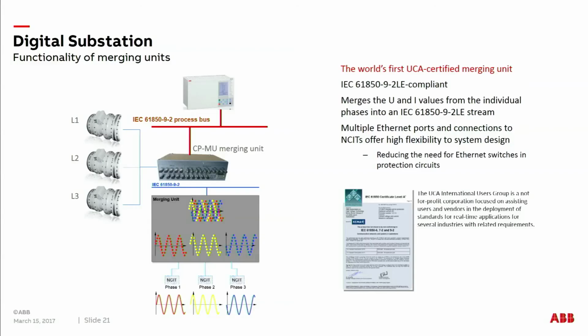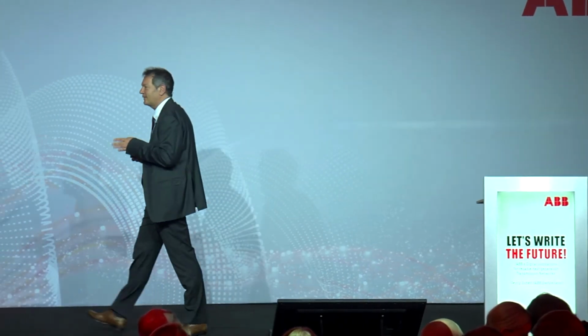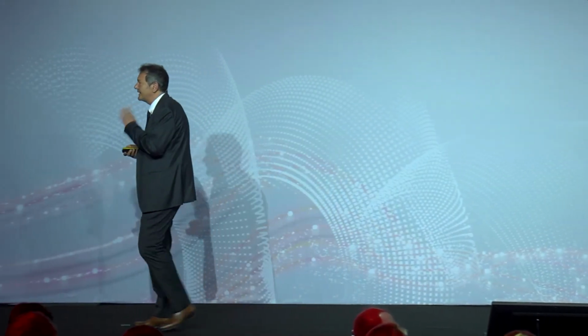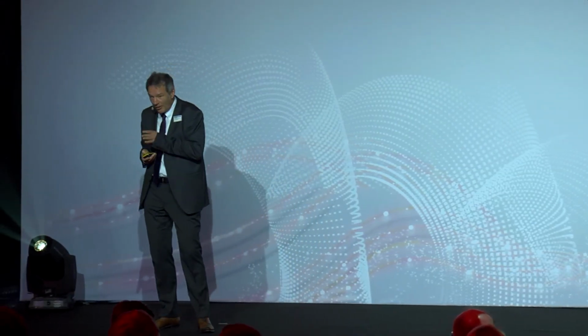Then, directly at the sensor, as I was saying, there is electronics, so there is some sampling. The output of the sensor is analog. With this analog signal, you go to this electronics, and in the electronics you have a sampler. So you transform the analog signal into a digital signal, and in the merging unit you then collect these sampled signals, package them and put them on this bus, which is standardized as IEC 61850-9-2. This is available. This is a technology which is now coming.